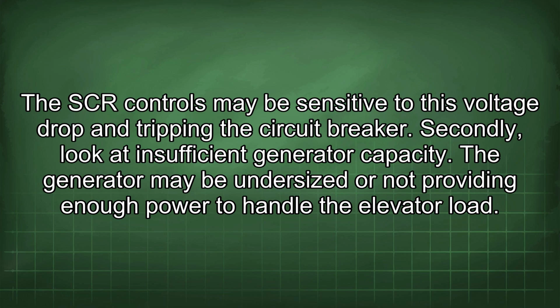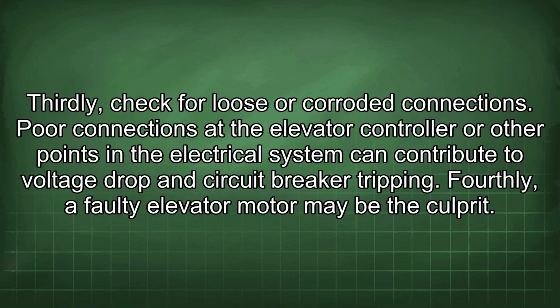Secondly, look at insufficient generator capacity. The generator may be undersized or not providing enough power to handle the elevator load. Thirdly, check for loose or corroded connections. Poor connections at the elevator control or other points in the electrical system can contribute to voltage drop and circuit breaker tripping. Fourthly, a faulty elevator motor may be the culprit.